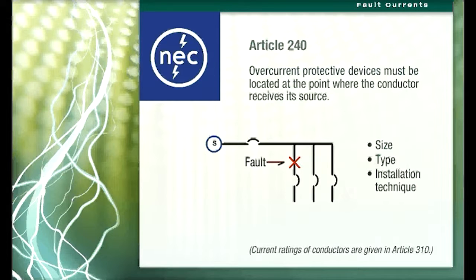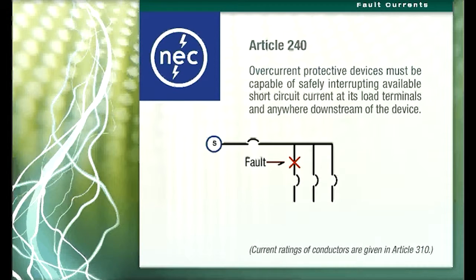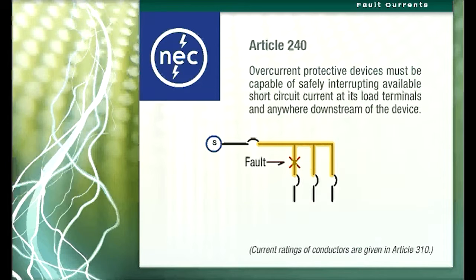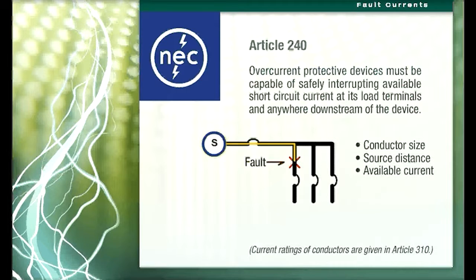The protection must be suitable for the size, type, and installation technique for the conductor. The current ratings of conductors are given in Article 310. Article 240 also requires that the overcurrent protective device be capable of safely interrupting available short circuit current at its load terminals and anywhere downstream of the device. The value of the short circuit current at any point in a circuit is a function of the size of the conductors, the distance from the source to the short circuit, and the current available from the source.